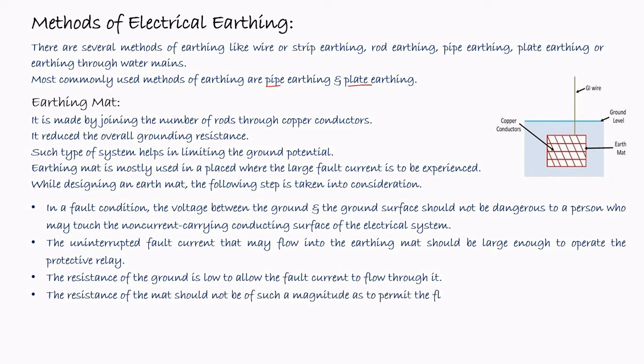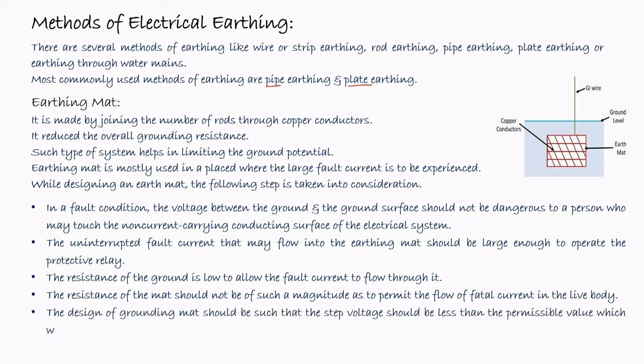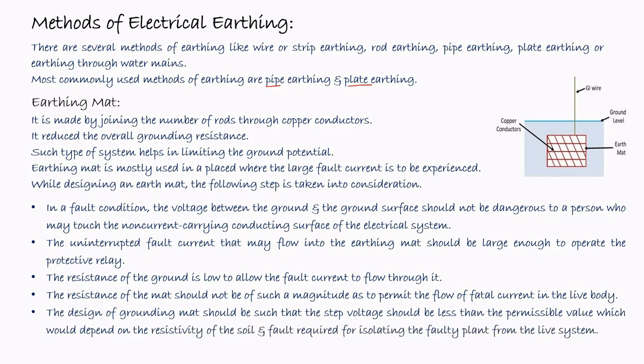The resistance of the mat should not be such a magnitude as to permit the flow of fatal current in the live body. Therefore, the concept is that the resistance of the mat and the resistance of the overall system should be as low as possible so that the fault current can easily be passed through the conducting wire. The design of the grounding mat should be such that the step voltage is less than the permissible value, which depends on the resistivity of the soil and the fault current required for isolating the faulty plant from the live system.